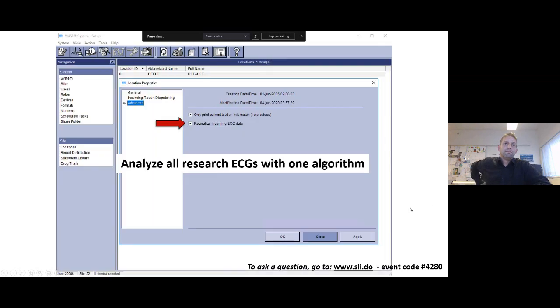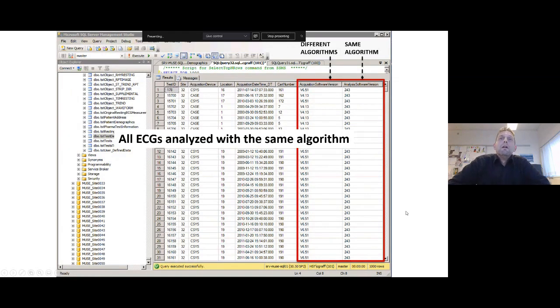So in our case, when we imported the 950,000 ECGs to MUSE, we use the reanalysis option that you can set in the system. This way, we make sure that all ECGs that end up in one site in the ECG database are analyzed with the same and the most recent version of the 12SL. So you can see here a before and an after picture, a before picture of the ECGs that we imported and an after picture. So in the left column in the rectangle is the version that was used to analyze the original ECGs by the ECG machines. And you can see that they're not all the same. And in the right-hand column, inside the rectangle, you can see that the version that we use upon reanalysis is all the same.